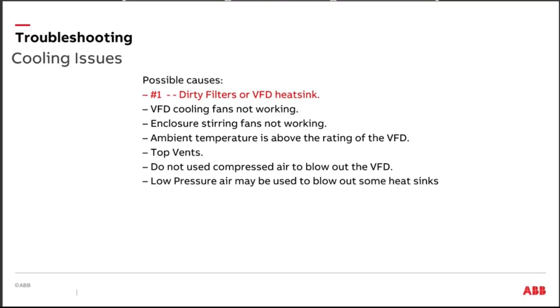Through the years, one of my habits that I've gained, especially back when I used to, well, even today, I shouldn't say that, even yet today, if I'm walking across with a lineup of drives, I might put my hand up, or I absolutely try to notice if I feel air coming out of the top vent. As you're walking through, if you've got 6 or 10 drives or whatever it is lined up in a row, and you have air coming out of them, and you step in front of one of them, and there's not air coming out of it, then you know, hey man, when I get ready to pull maintenance, I need to check this thing. You might even want to go look on your keypad and see what your temperature of your drive says it is. Notice stuff like that.